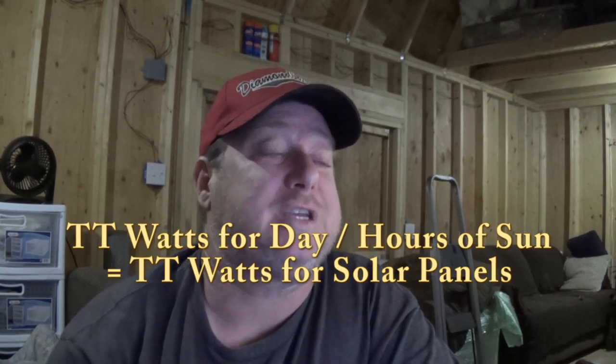So that's another way of calculating it: 6,573 watts for the day, divided by 5 hours of sunlight that you're going to get, will give you your total watts that you need for the day. Now you just divide it by whatever panel size you can find. So if you find 300 watts, divide by 300. If it's 260, you'll divide by 260.